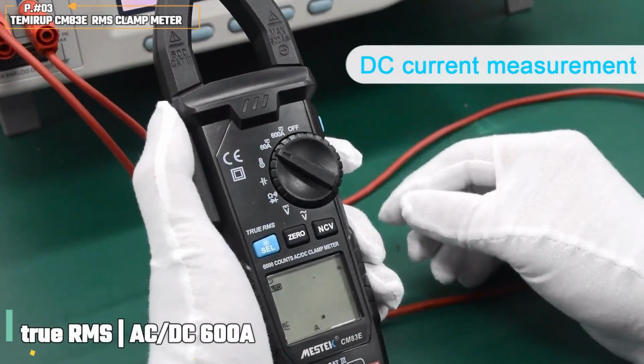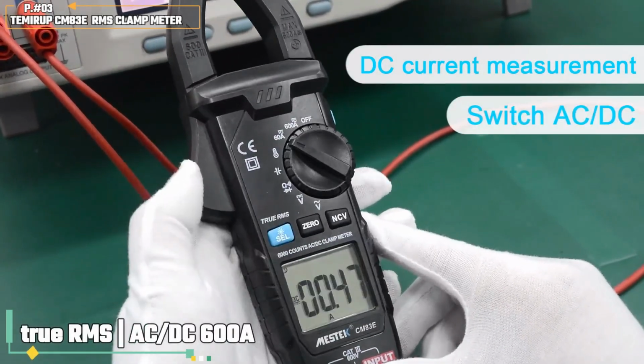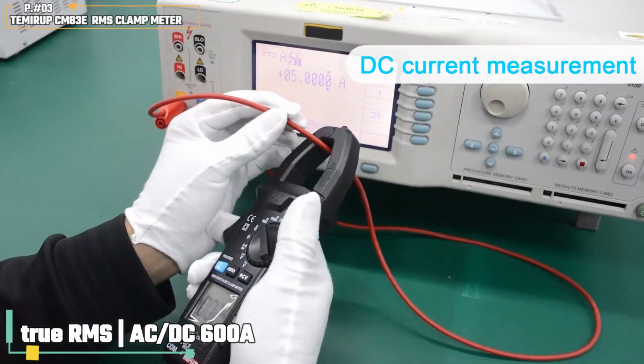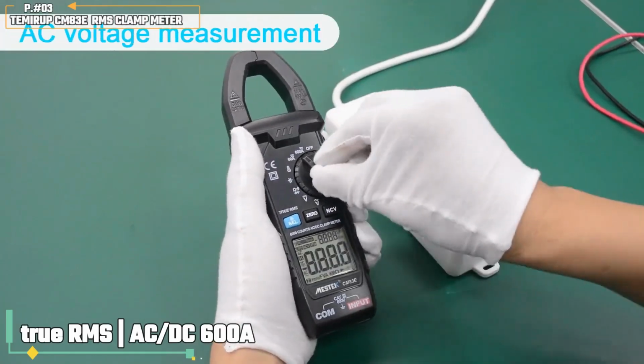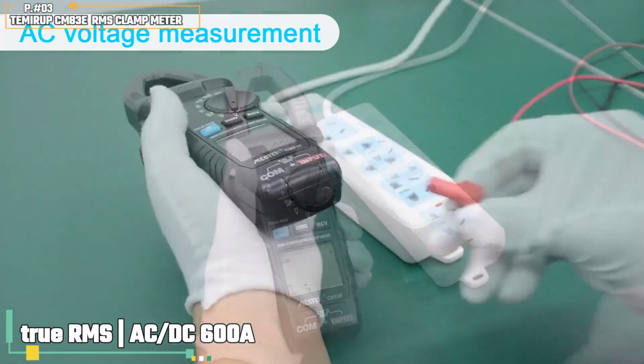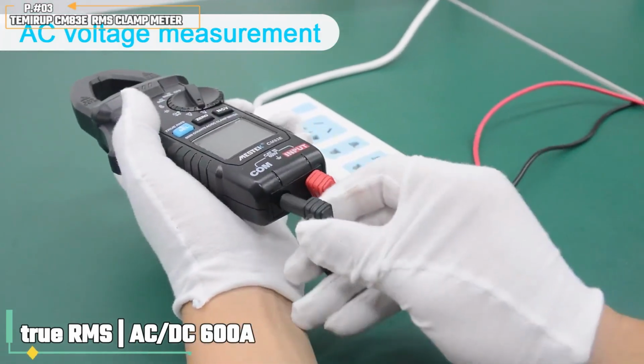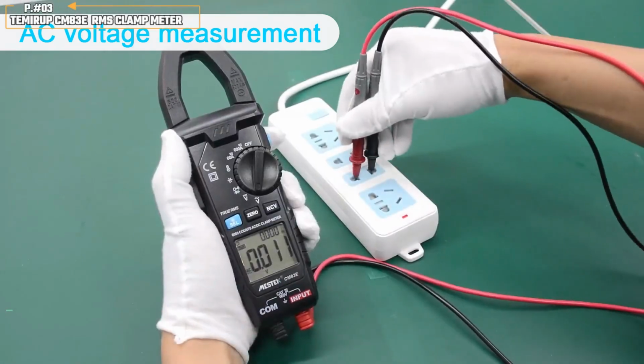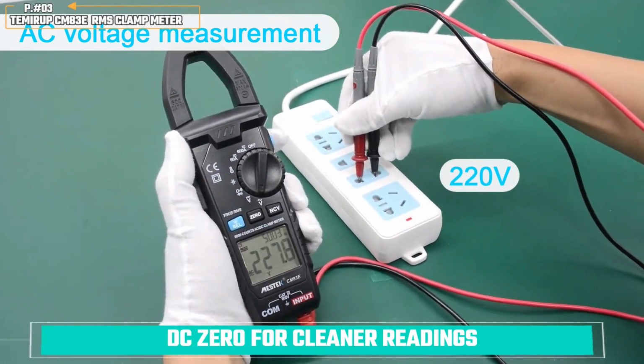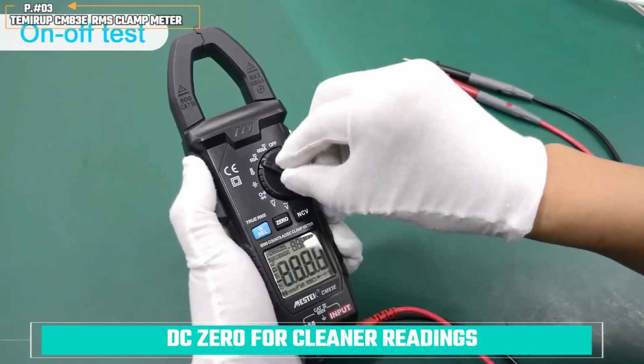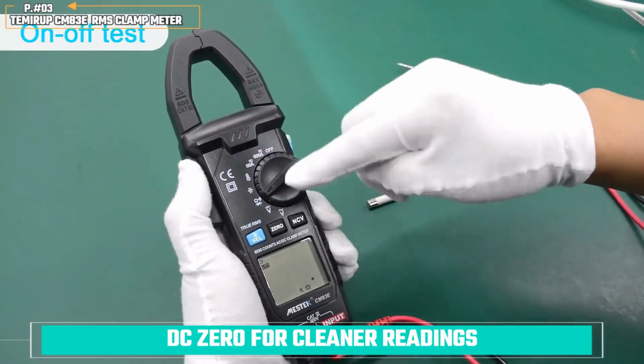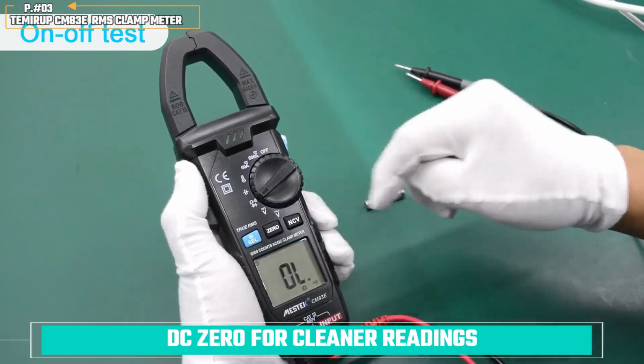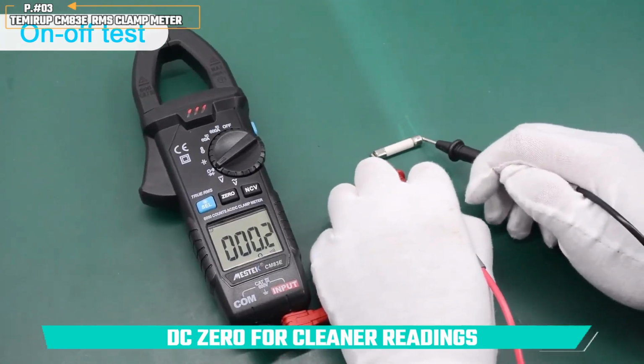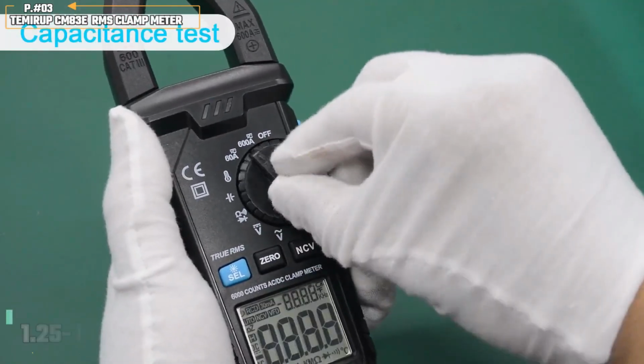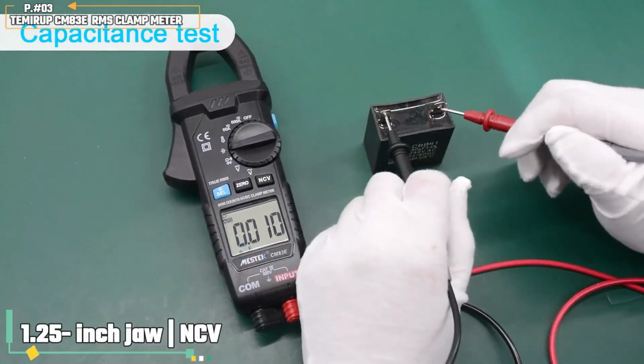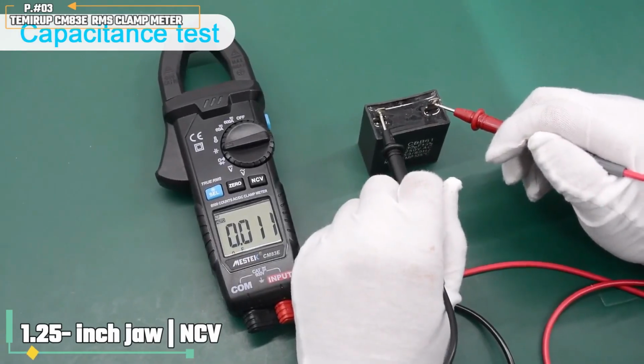The 6,000 count True RMS system measures both AC and DC current up to 600 amps. True RMS improves AC readings on nonlinear loads, while the DC capability supports battery, charging system, and other direct current checks. Before measuring DC current, the zero function lets you remove environmental magnetic offset from the reading. This helps establish a cleaner baseline, especially when checking smaller changes in DC current. The jaw opens to roughly 1¼ inches, providing room for individual conductors without disconnecting the circuit.